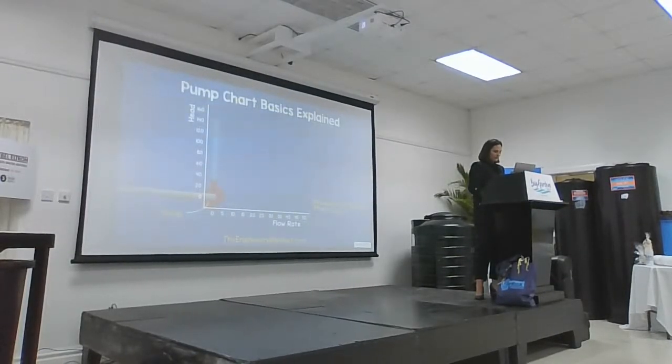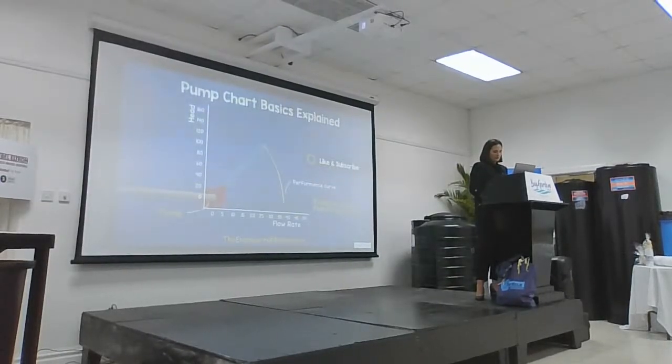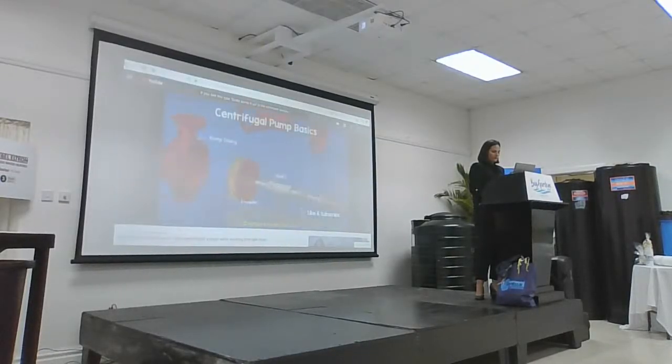At this point, it's just spinning the same bit of water, which isn't good for the pump, so you don't want to run a pump like this in the real world. By recording the values during the elevation, we basically get a pump curve, although I will note that pump manufacturers don't test pumps this way because it's just not practical. If you want to know how a centrifugal pump works, then we have covered this in detail in our previous video. Do check that out, links down below.